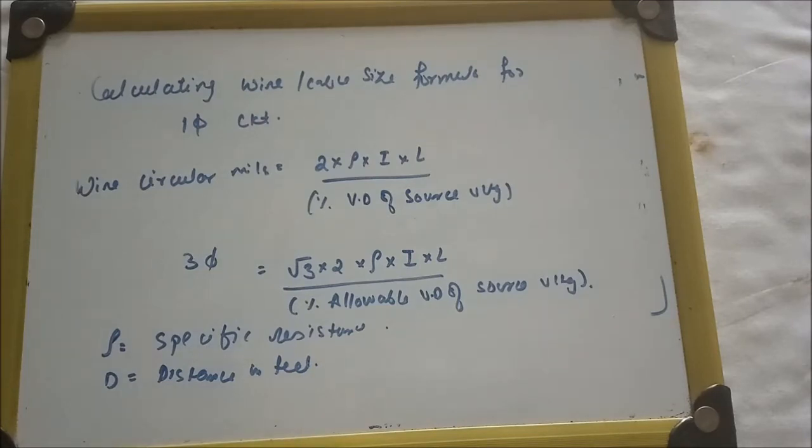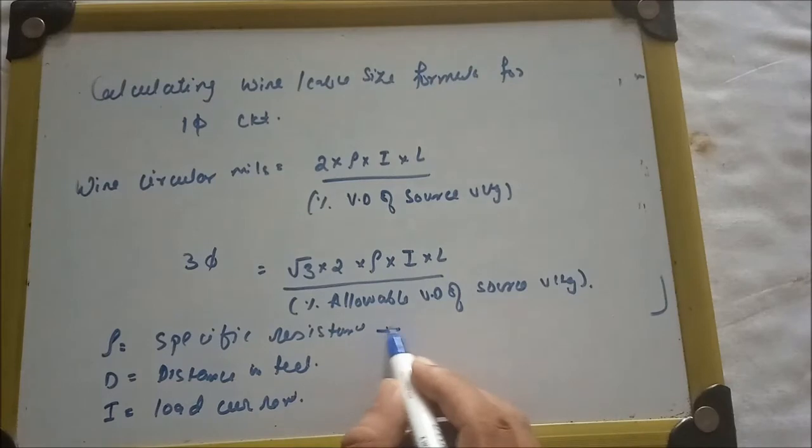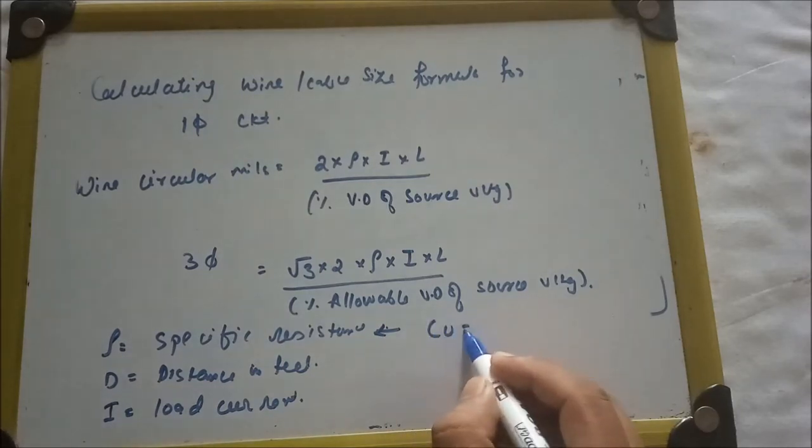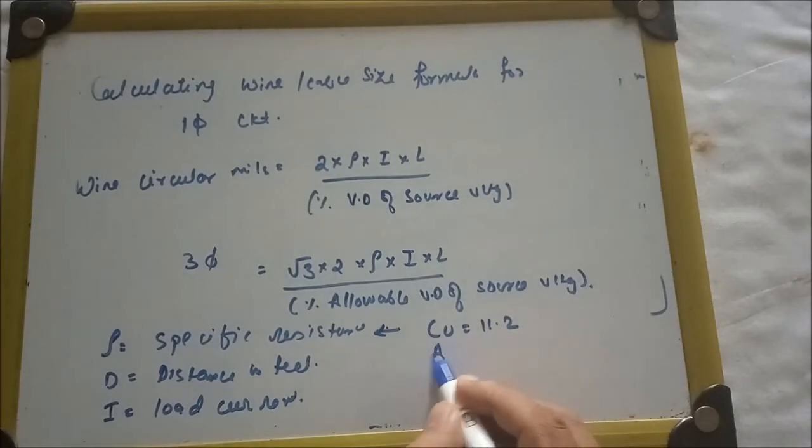I is equal to load current. For specific resistance of a conductor, for copper and aluminum: for copper it is 11.2 and for aluminum it is 17.4. So this is the formula for calculating the wire or cable size.